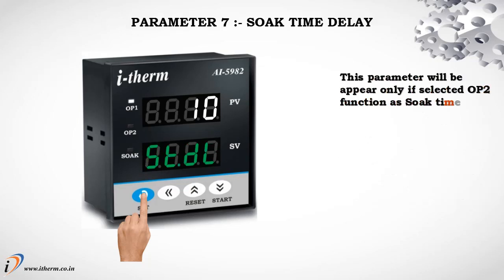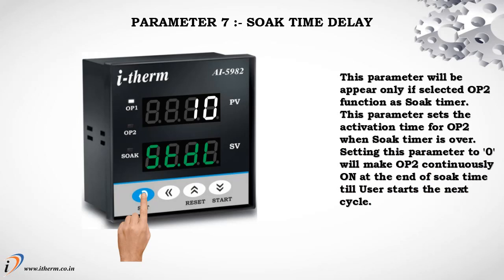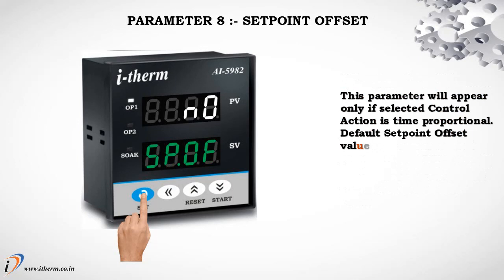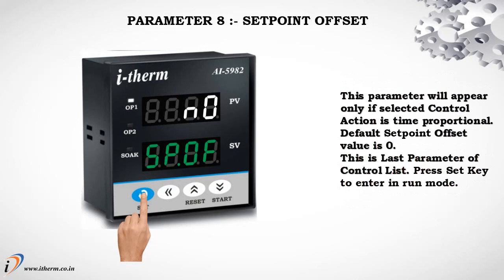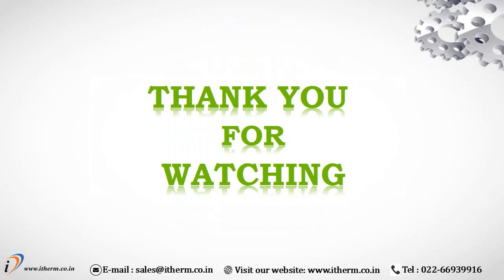Parameter 7: Soak Time Delay. This parameter will appear only if output 2 function is set as Soak Timer. It sets the activation time for output 2 when the Soak Timer is over. Setting this parameter to 0 will make output 2 continuously on at the end of Soak Time until the user starts the next cycle. Parameter 8: Set Point Offset. This parameter will appear only if the selected control action is time proportional. Default set point offset value is 0. This is the last parameter of the control list. Press Set key to enter Run Mode. Thank you.